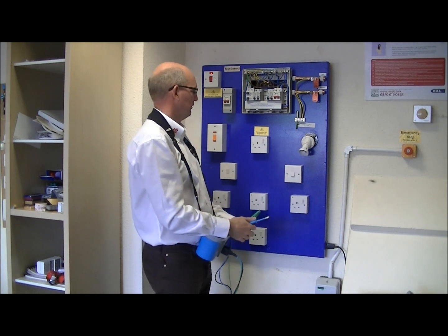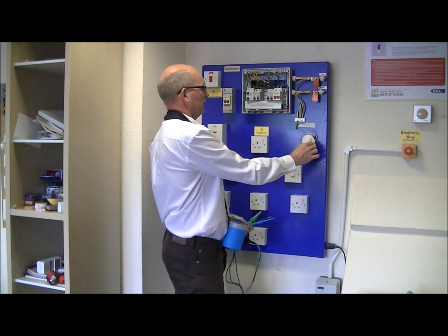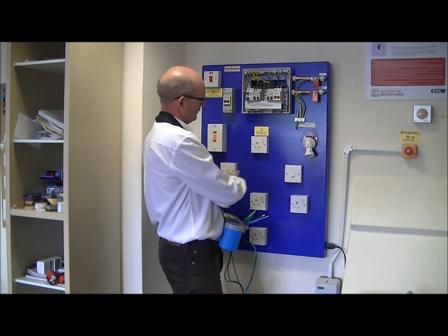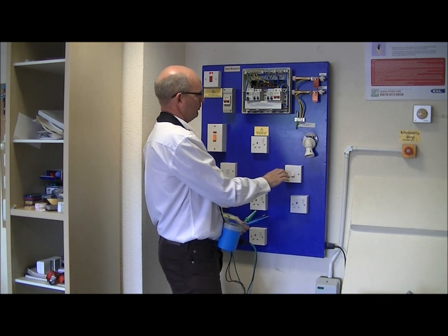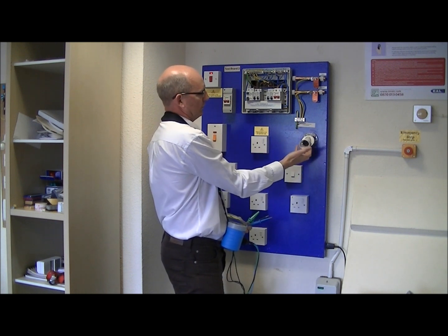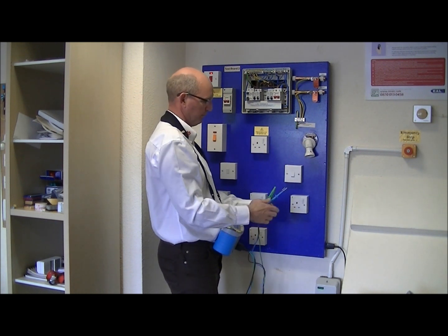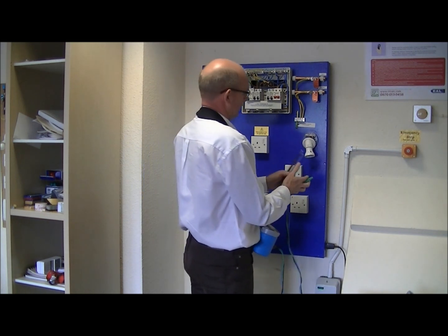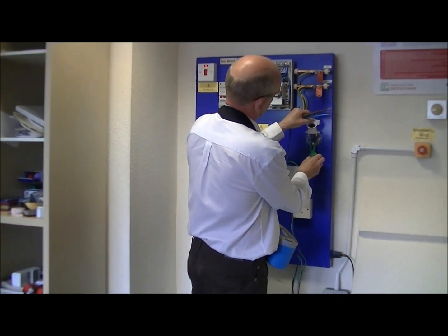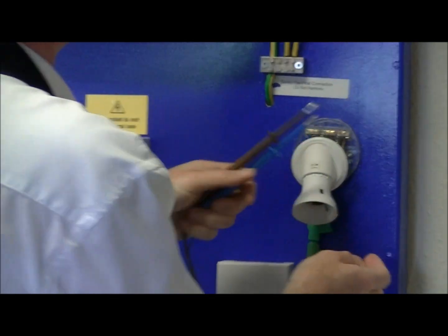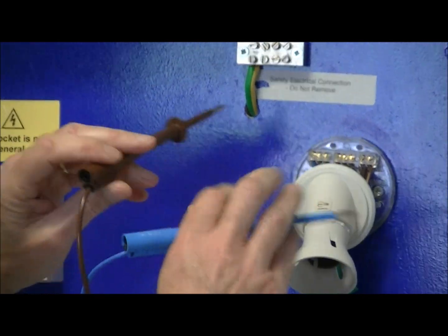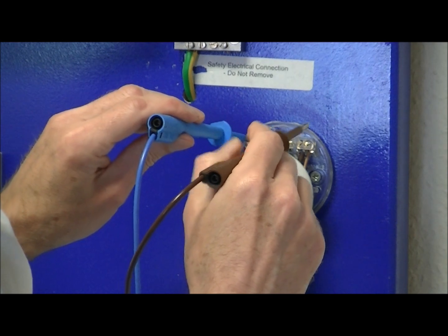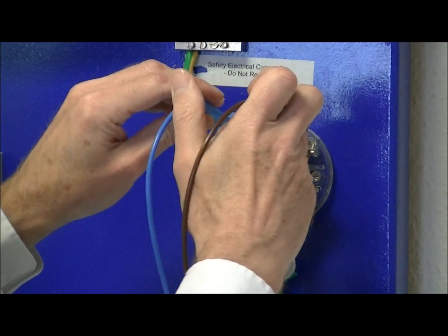So in order to carry out this test, we need to establish the furthest point. In this case I'm going to demonstrate where to measure on a lighting circuit. So we have a two-way lighting circuit, and the furthest point on that will be the output to the lamp. So again, 3 leads with this meter. So we connect the earth lead to the CPC of the circuit, furthest point, and then we're going to connect across the line and neutral to the lamp in the ceiling rose, like so.